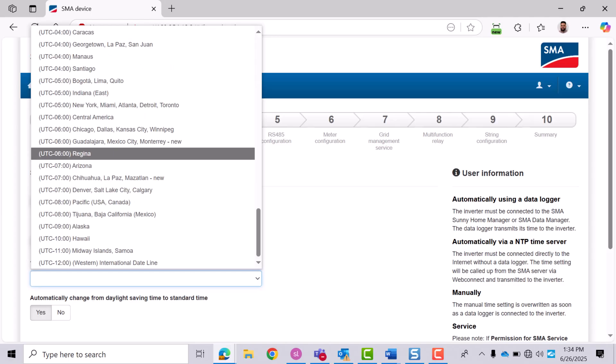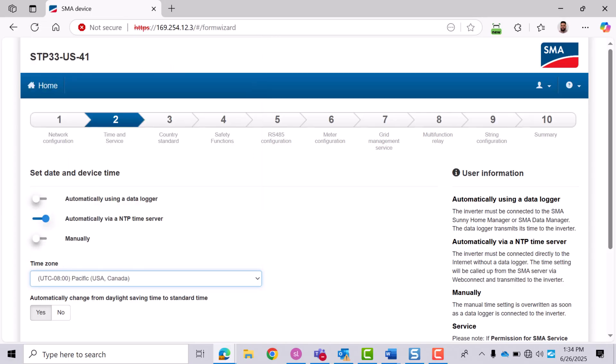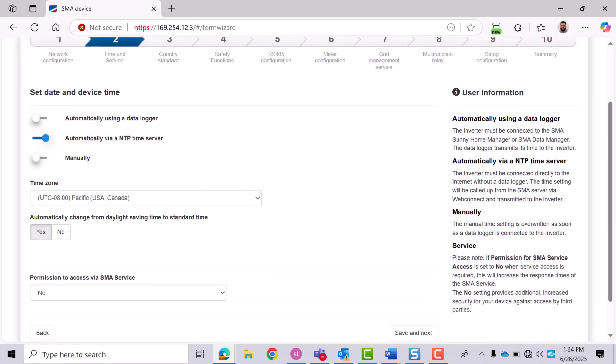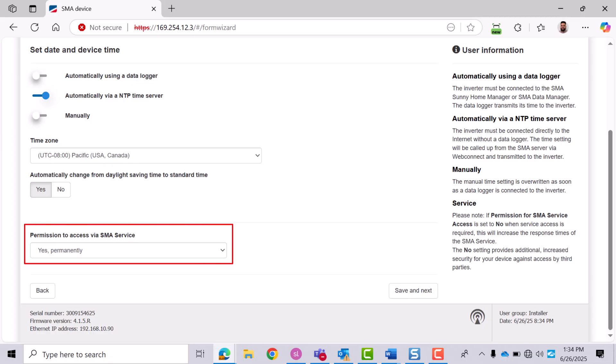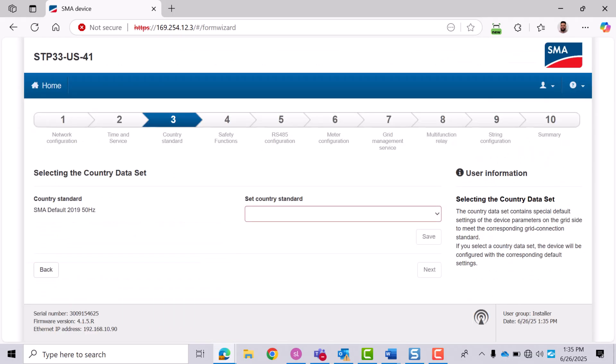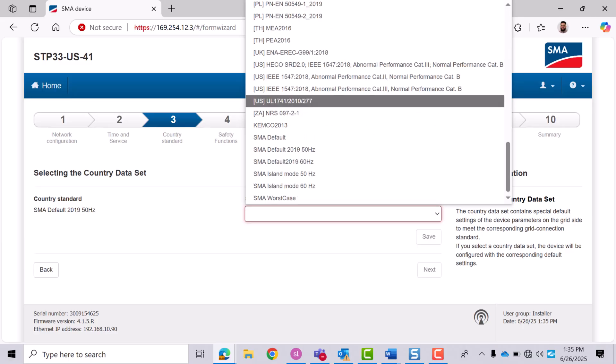To sync time automatically, make sure the inverter is connected to the internet. To save yourself time with our service team, ensure you select yes from this list. Click Save and Next. Select the correct grid standard for your region. Click Save and confirm the selected standard appears in the list.